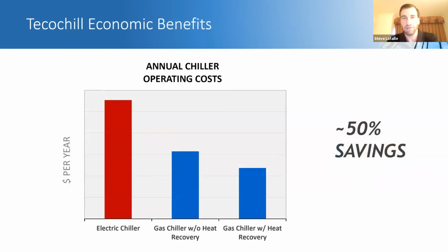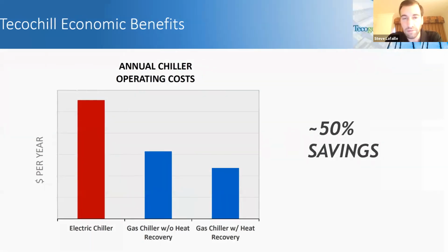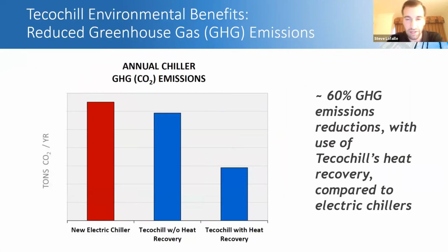This is a rough example of how the math works out. You can see about a 50% reduction in operating costs is very common over an electric chiller. Using the waste heat gets you a bit more of a bump lower, but even when you don't, generally just the difference in fuel costs gets you savings, and a big chunk of that savings is usually demand.